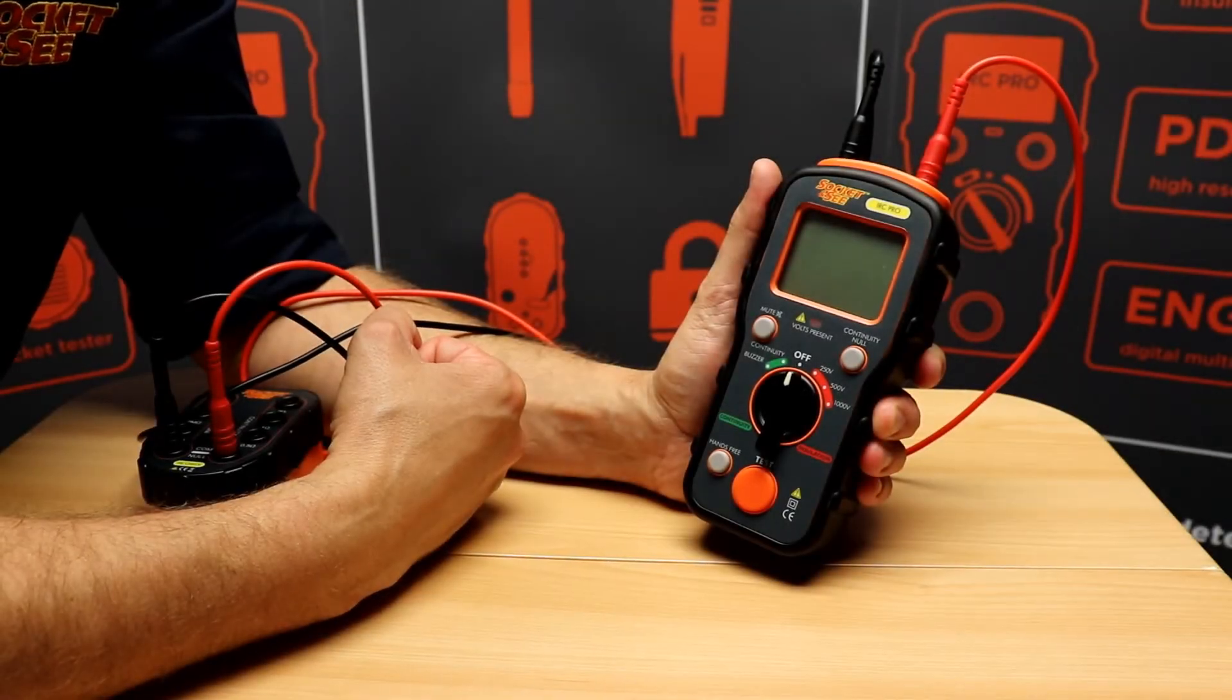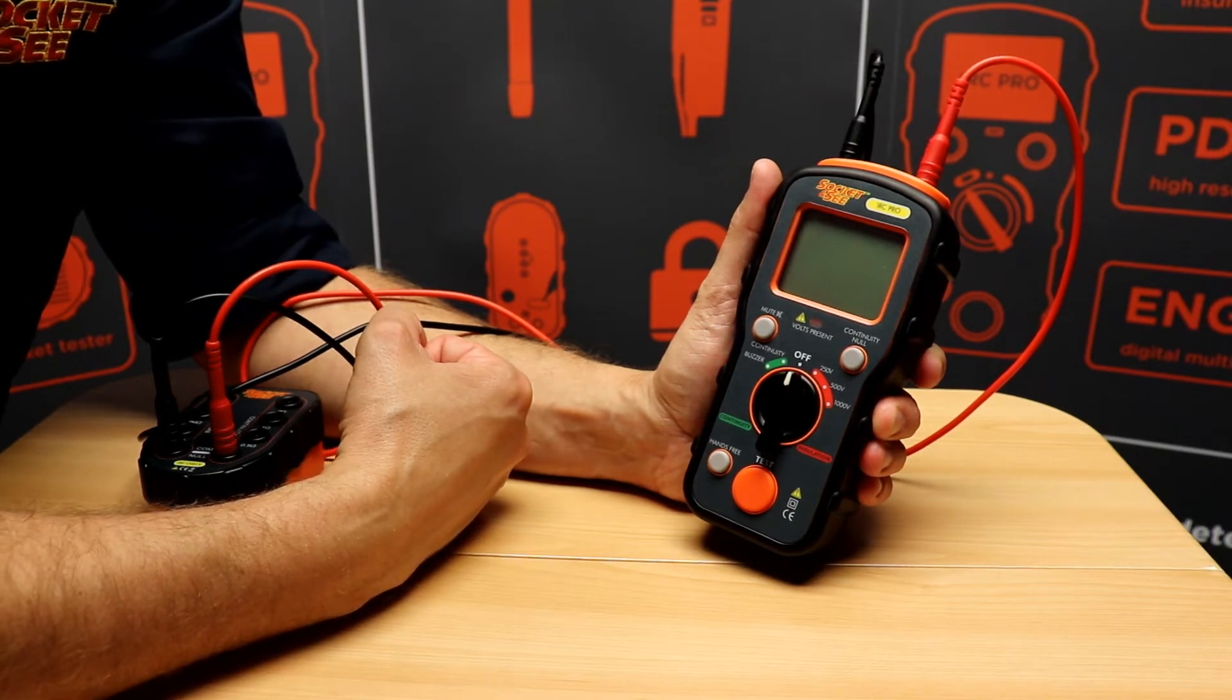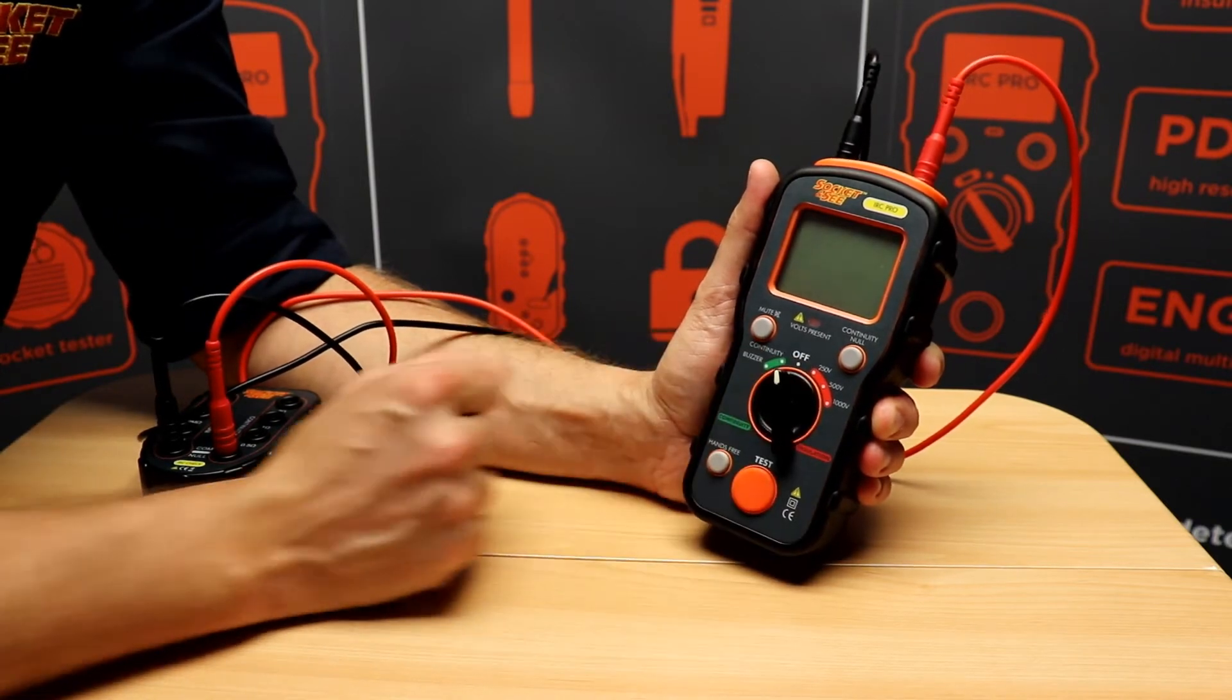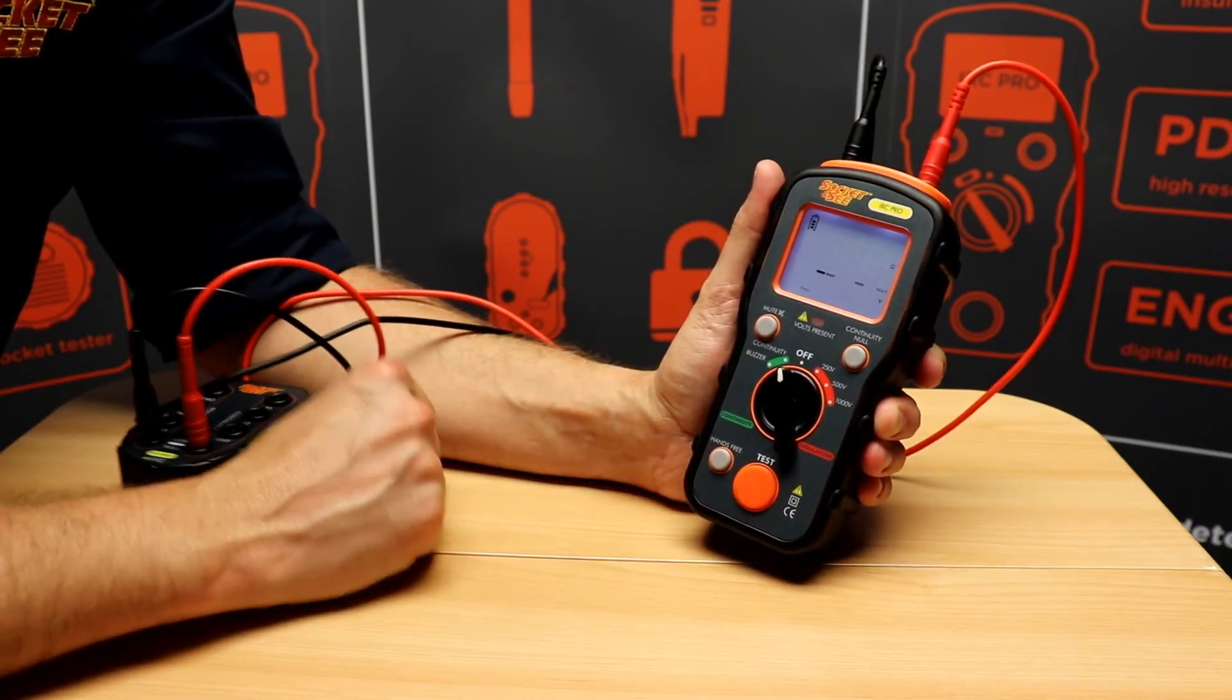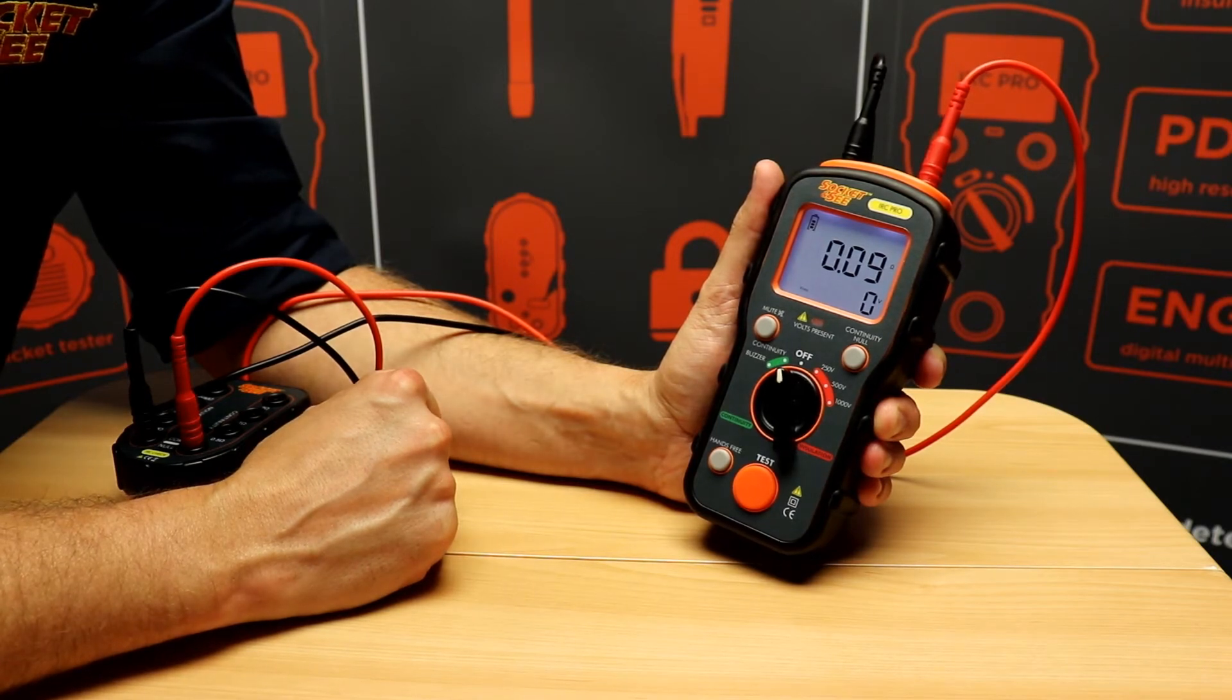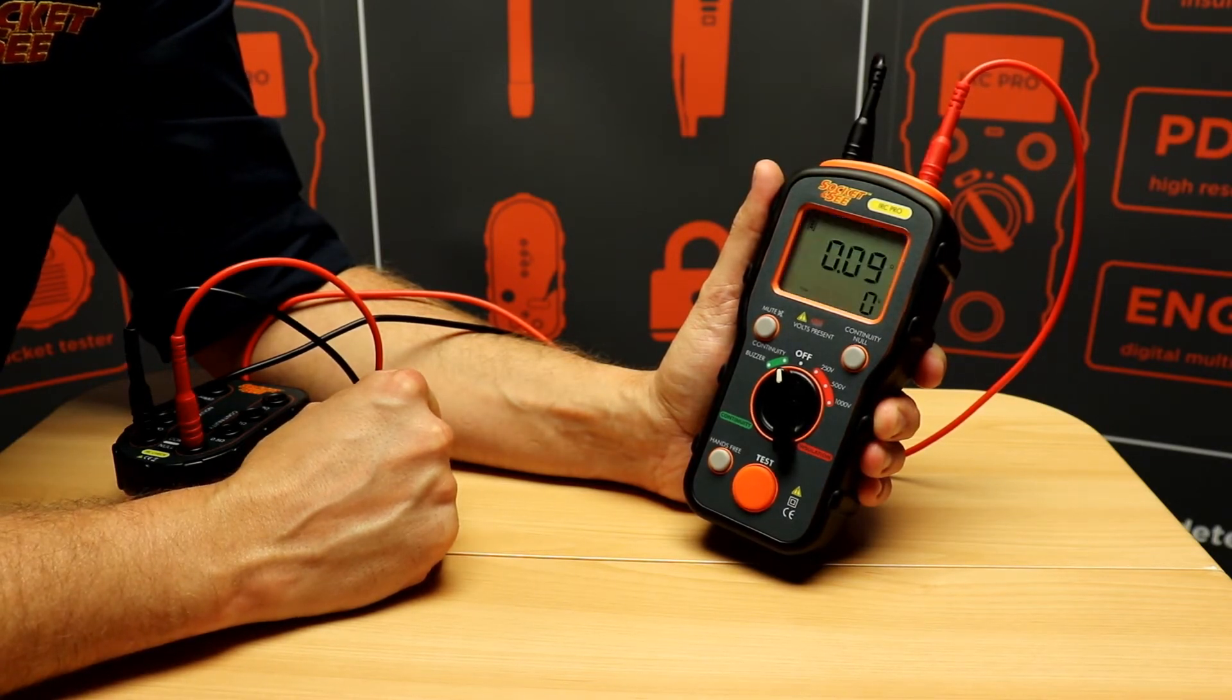We're going to look at the feature set on the Socket & See IRC PRO Insulation and Continuity Tester. Firstly we'll switch to Continuity. We then press Test. We measure 0.09 ohms. That's the resistance of the test leads.